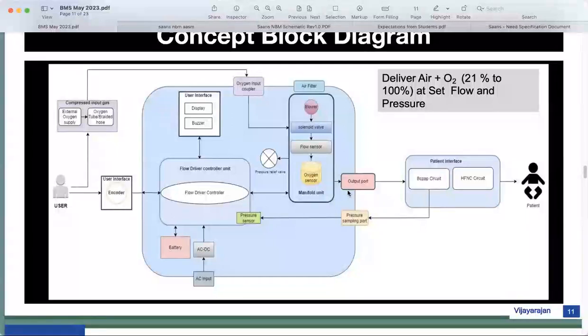The resistance means it puts back pressure. It reduces the flow. So not only do you have to generate air-oxygen between 21% and 100% at a set flow and pressure, a certain amount of flow is required. You can understand flow like this: you stand in front of a fan, so you get a lot more air, correct? That's called flow. Pressure helps you keep the air pathway at an expanded position. The doctors know what type of pressure and flow we need to provide, and what level of oxygen they require. So it's simple. It's a controller mechanism with physics added to it.